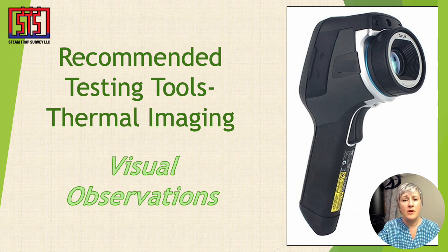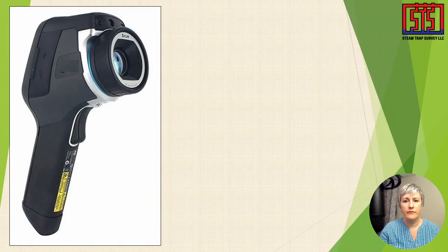Verify the steam traps are installed correctly. Float and thermostatic and inverted bucket steam traps should be installed plumb. In most cases, unless a condition problem can be clearly determined visually, testing traps by ultrasound and thermography will be necessary to provide a correct diagnosis.